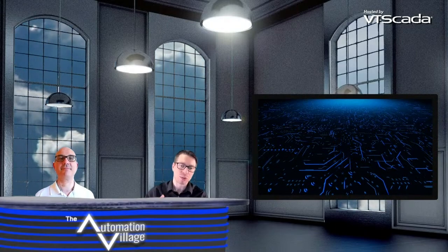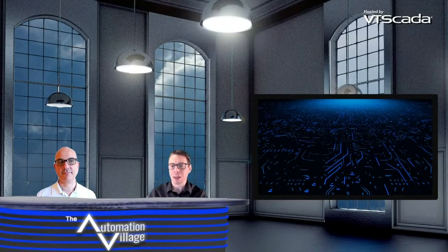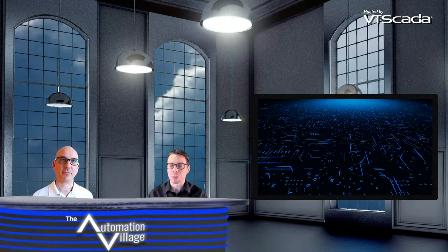In the meantime, I just want to reflect back on some of what Jenny had shown there. I really like that high performance widget, that bar graph that has the trend in it. It's got the value, you can put in the expected value, so if it's taking time to go to a set point, you can put that in, and also that expected range. I think the expected range is my favorite part of that, because somebody who doesn't know anything about the system can go in and see not only if you're in or out of an alarm, but if you're outside of a typical condition, and that makes it pretty notable.